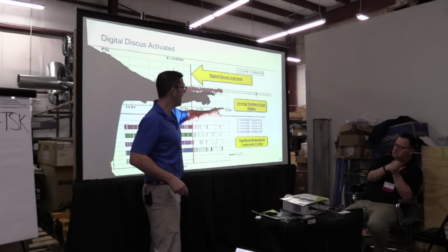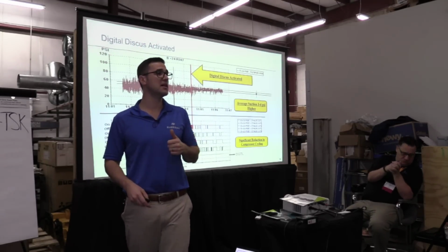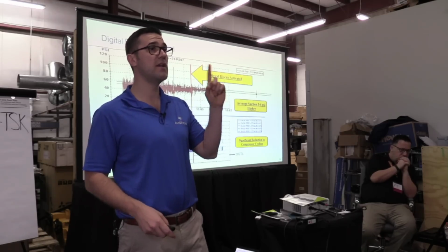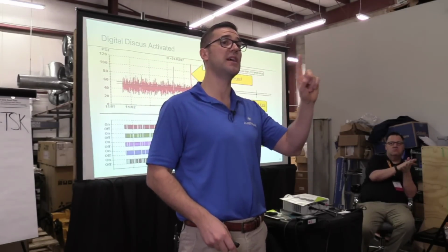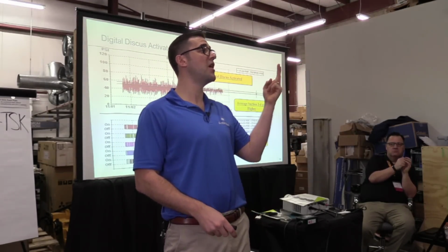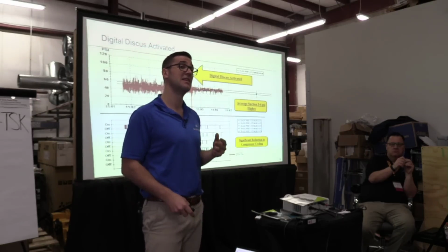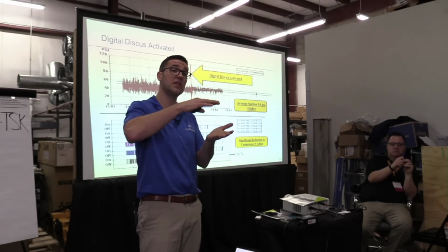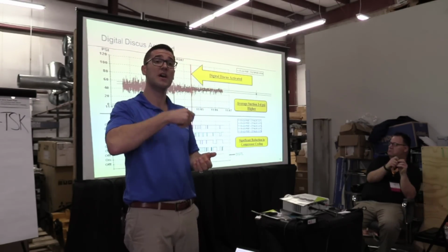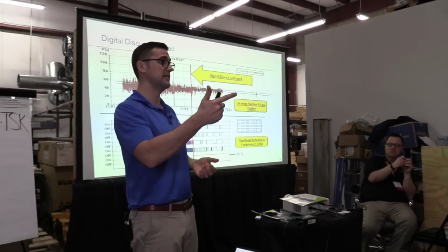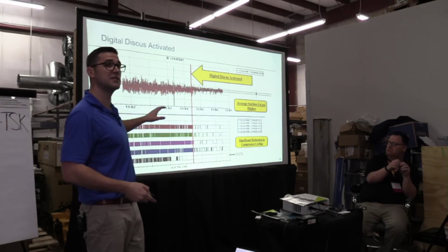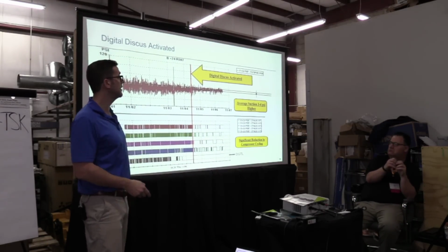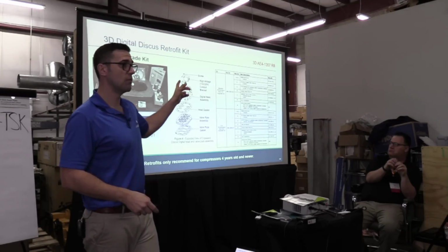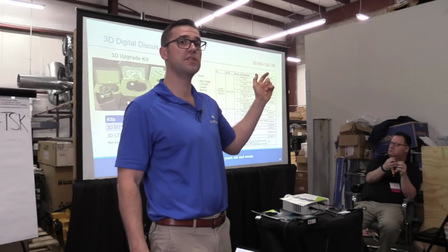And look at this. Average suction pressure up 3 to 4 psi. A rule of thumb is that for every 1 psi increase in suction, you get approximately a 2% efficiency gain. That's your compression ratio that Don talked about earlier. Reducing that compression ratio means less work, less heat. Everybody understand that? Excellent.